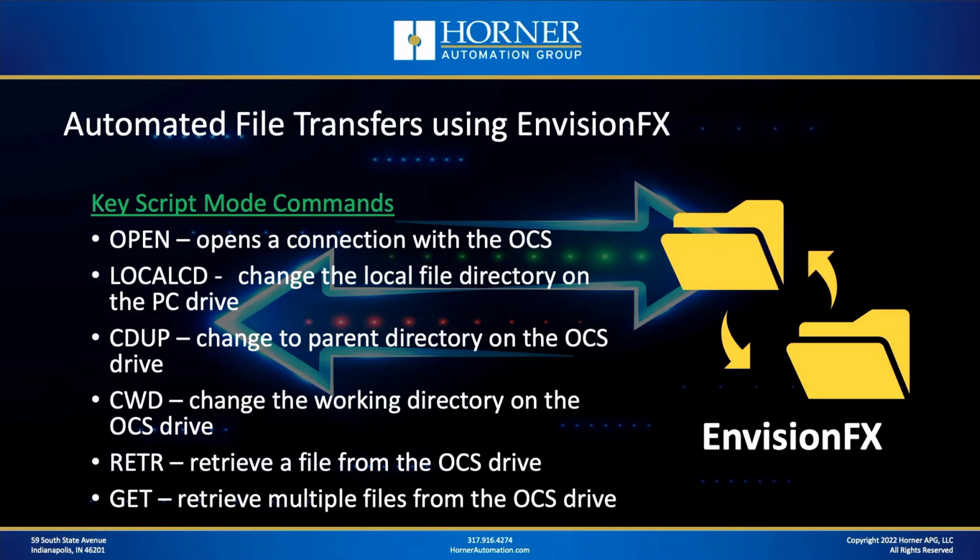And then there's a cwd command. That changes the working directory on the OCS drive. We'll use that to change to our send directory, for instance, so that EnvisionFX can find the files it needs to upload. When we upload files, we can either use the retr command, which retrieves a single file from the OCS, or a get command, which we can use to retrieve multiple files. If we retrieve multiple files, we need to use wildcards like star.star and question marks to specify the specific files that we want to get.